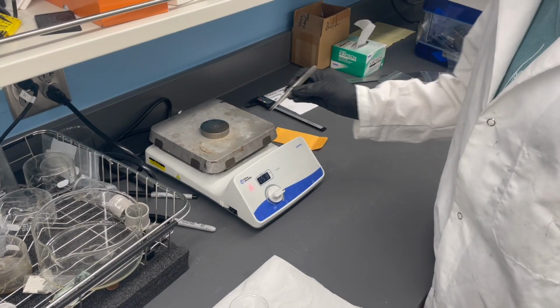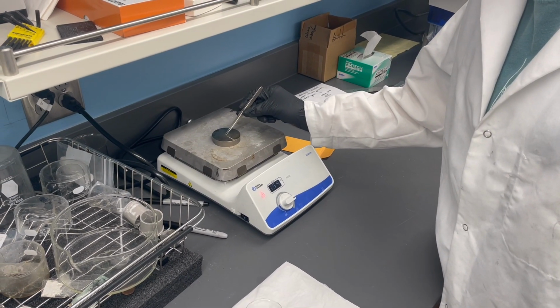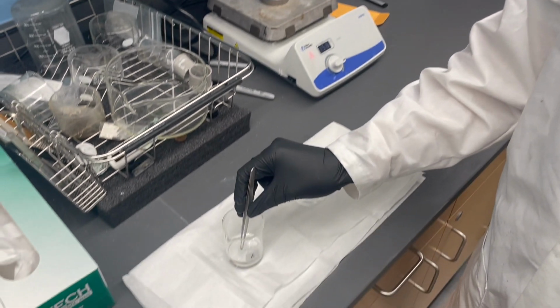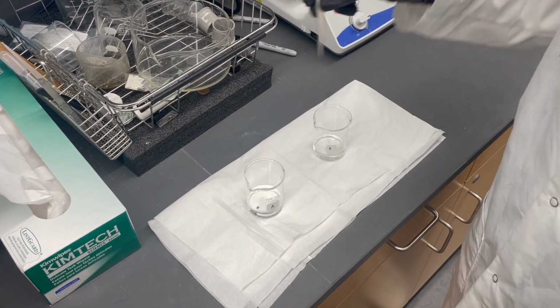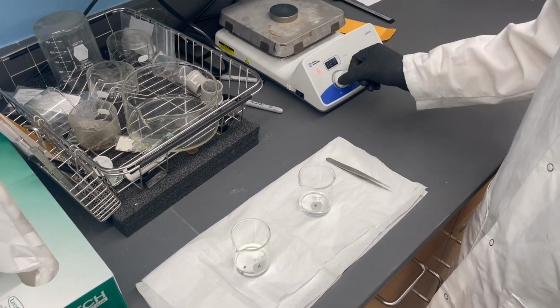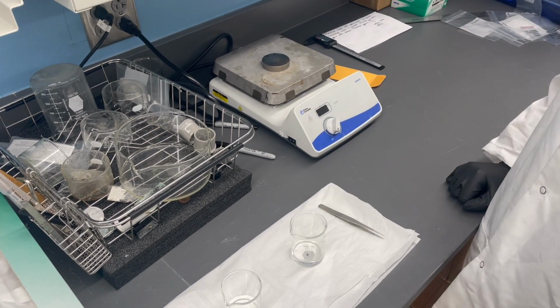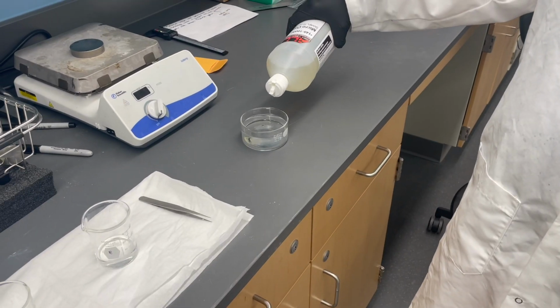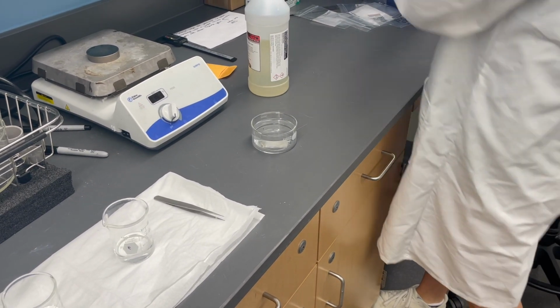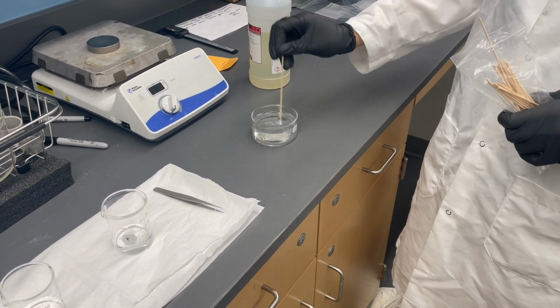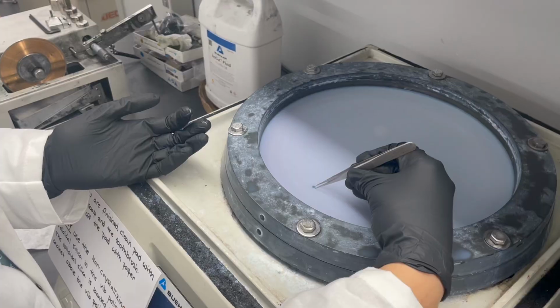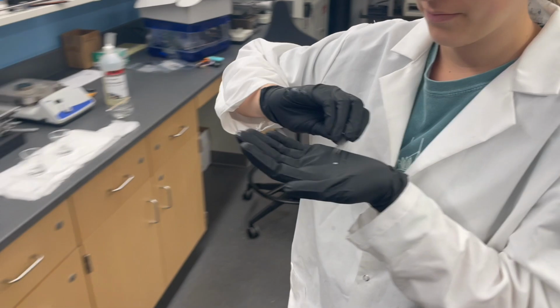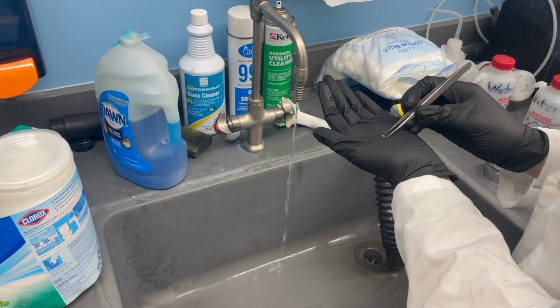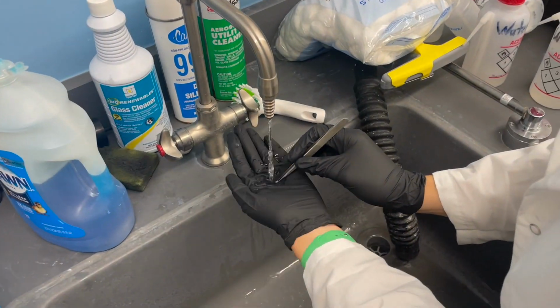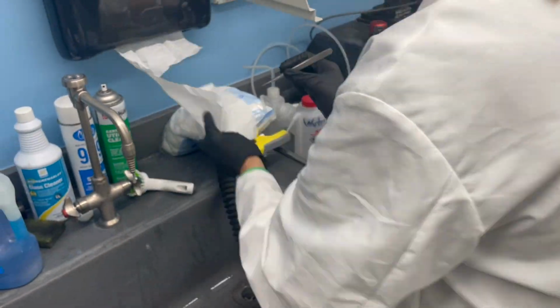After confirming the sample has a mirror finish, heat the polishing fixture to melt the crystal bond. Using tweezers, gently remove the sample and place it into the acetone beaker. The acetone will remove any residual crystal bond on the sample. Fill another dish with water and microorganic soap, mixing with a cotton swab. Use the tweezers to take the sample out of the acetone and place it polished side down in the colloidal silica left in the vibratory polisher and gently move it around using your finger. Then bring it back to the sink and gently rinse with water.